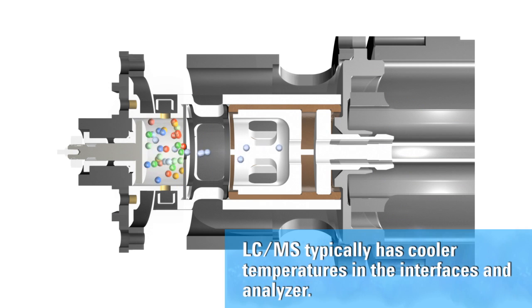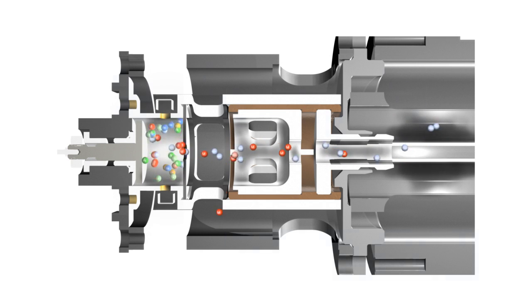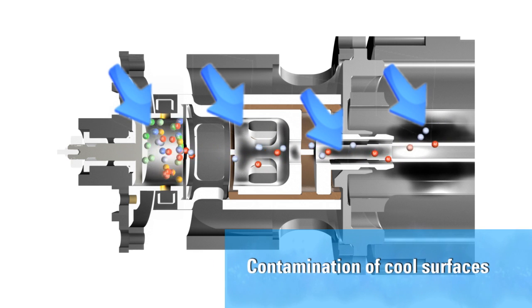For an LC atmospheric pressure source like ESI, metal quadrupoles at temperatures of 100 degrees Celsius are perfectly adequate and commonly used. But for GC-MS-MS analysis, metal surfaces at this temperature will quickly become contaminated.